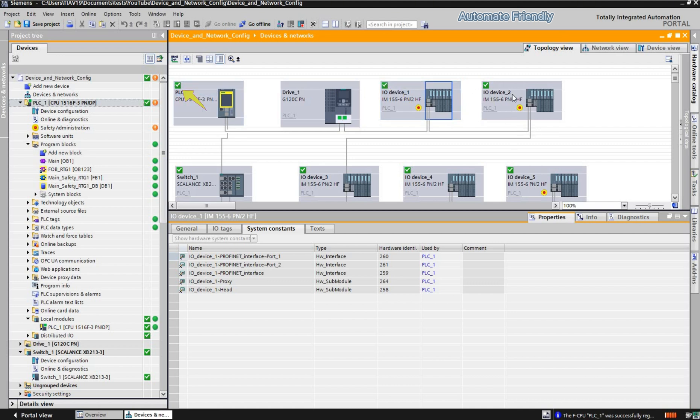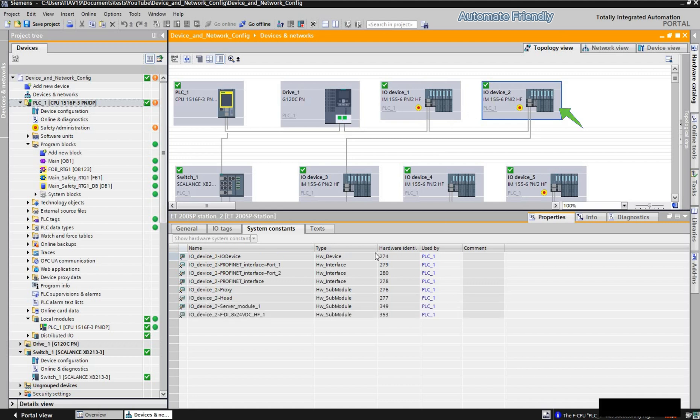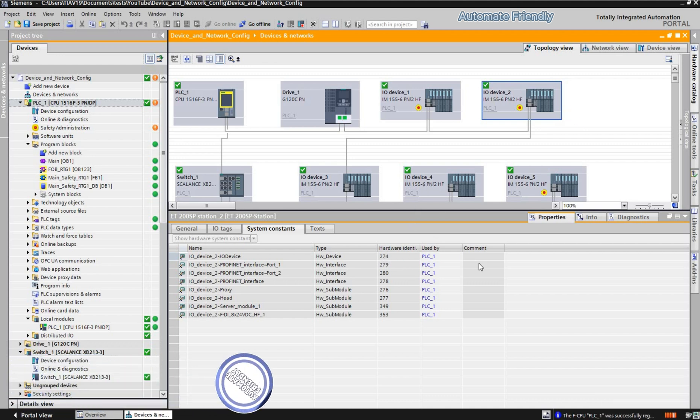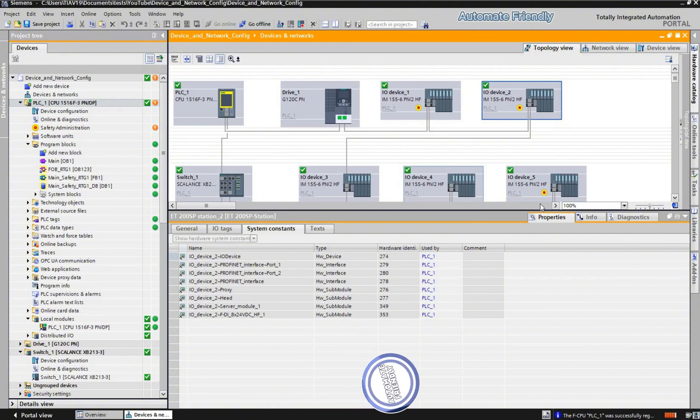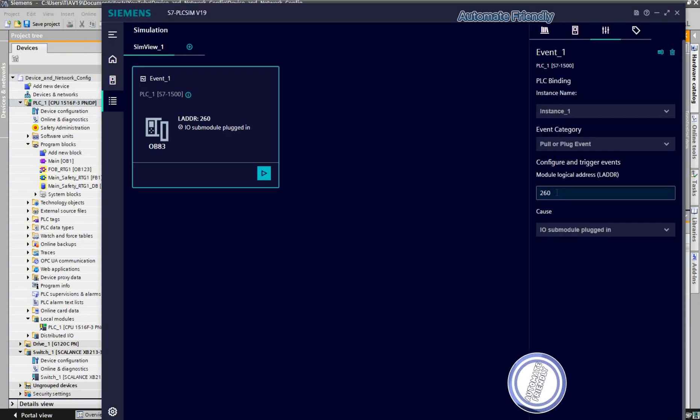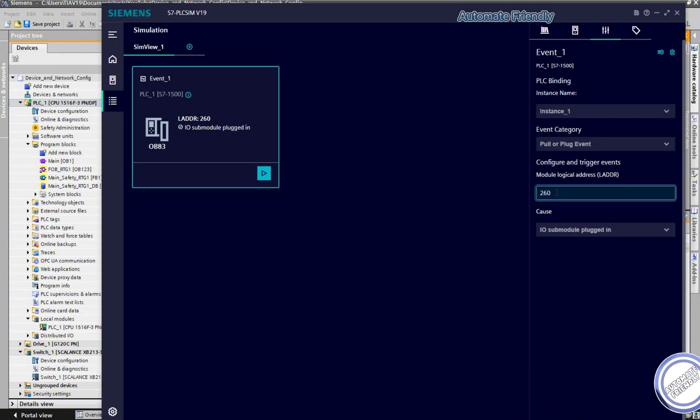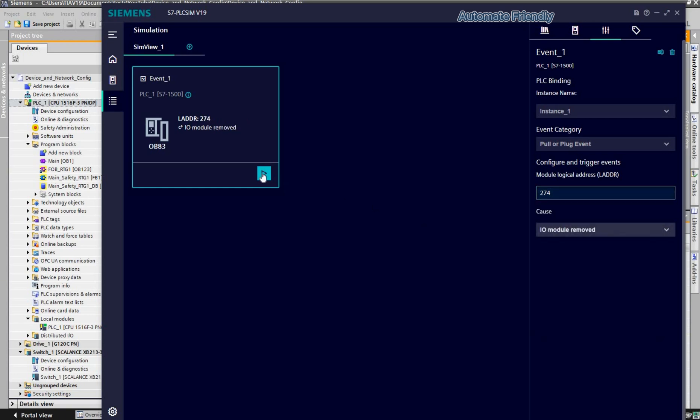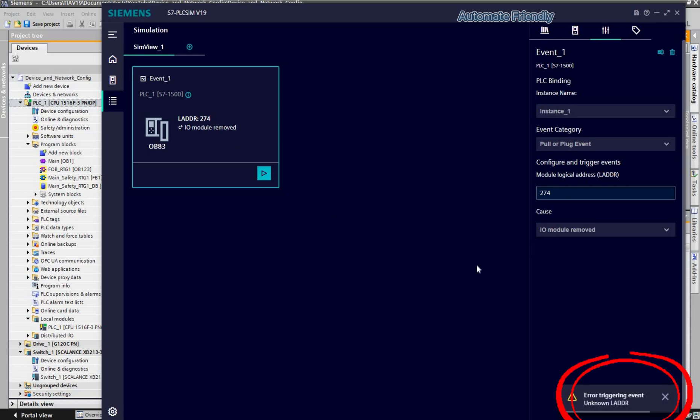Let's try to see a sample error when triggering an event with the wrong identifier. On IO device 2, I will select a non-Profinet interface hardware identifier 274 and trigger a module removal. When the play button is clicked, an error indicating an unknown address is seen.